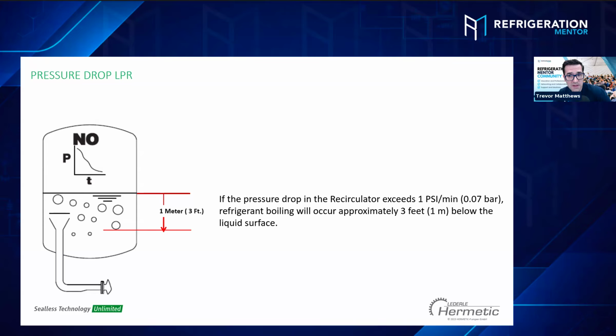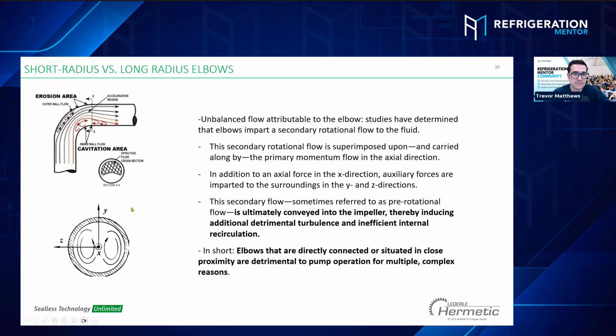Either way, like a compressor, you do a little bit of damage. That damage doesn't go away. It stays with the motor until maintenance repairs or replaces it. The rule is don't exceed 1 psi per minute in ammonia or CO2, 1 psi per minute. Don't exceed it.